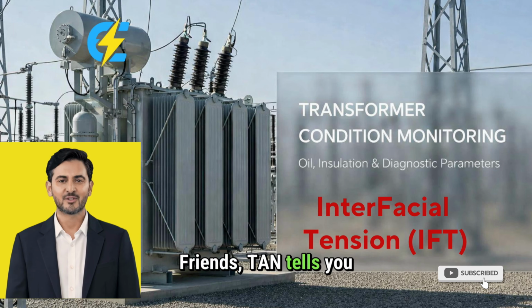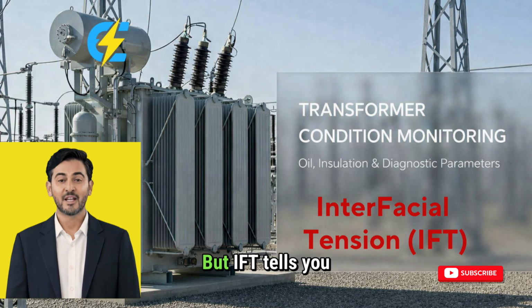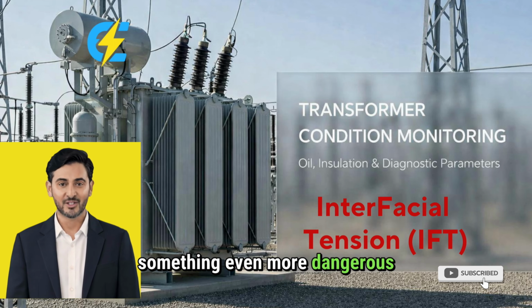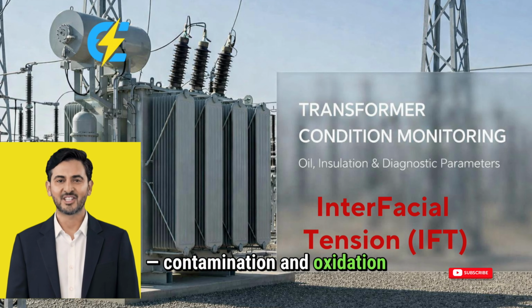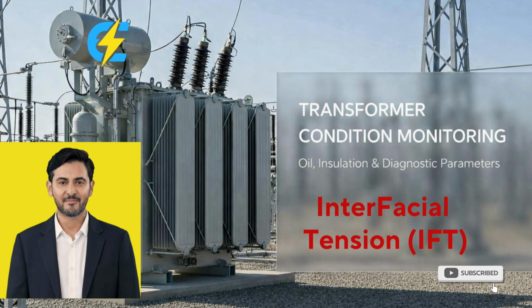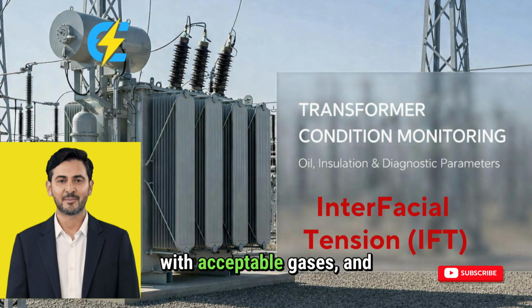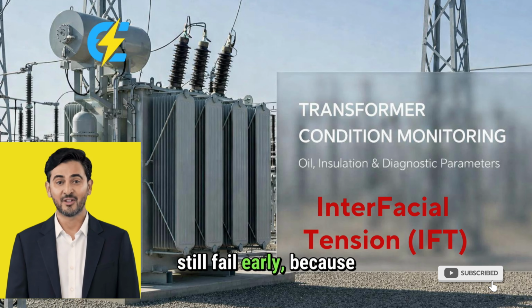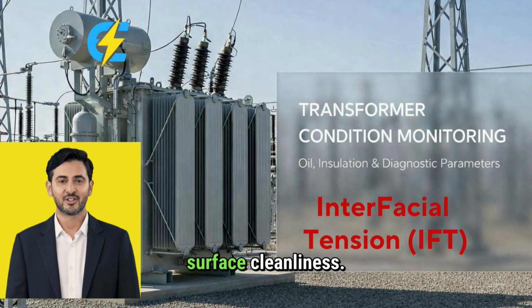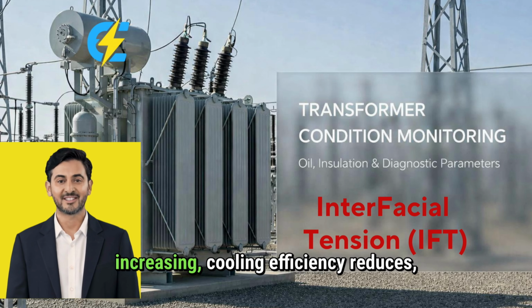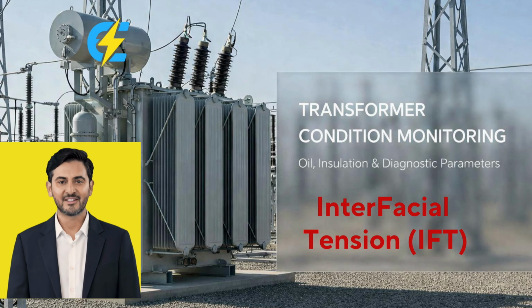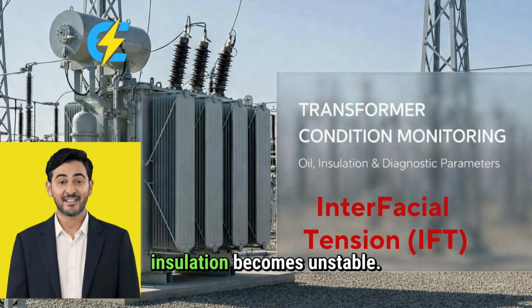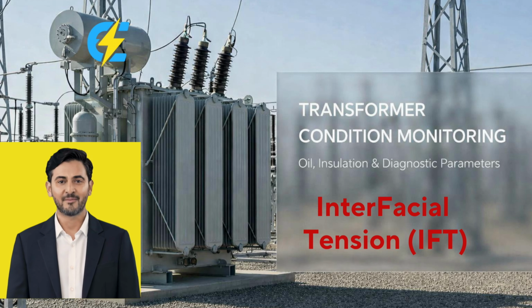Friends, TAN tells you oil is becoming acidic, but IFT tells you something even more dangerous: contamination and oxidation byproducts that lead to sludge formation. A transformer can run with acceptable gases and still fail early because the oil loses its surface cleanliness. That is exactly what IFT measures. When IFT drops, it means polar contaminants are increasing, cooling efficiency reduces, paper aging accelerates, and insulation becomes unstable.